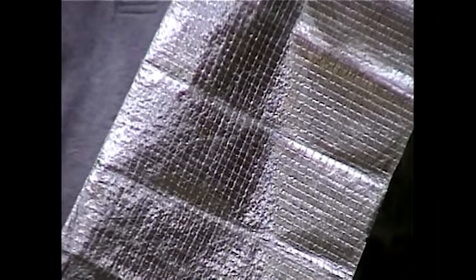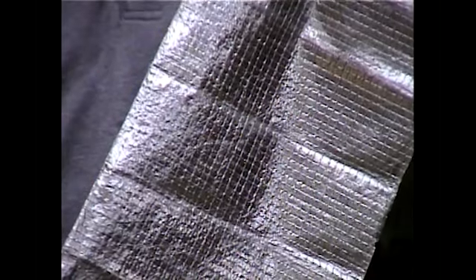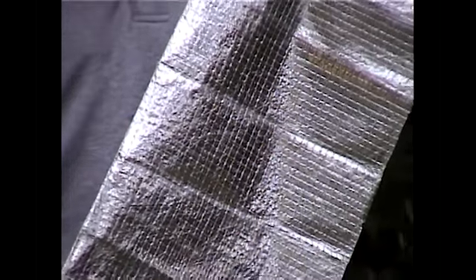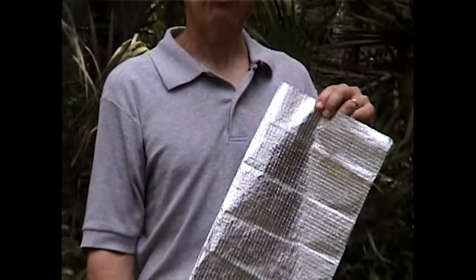In existing homes, you can add radiant barriers under the rafters to reduce heat gain. It works by reflecting heat back towards the roof. The heat can then exit the ridge vent. In the process, this creates a natural flow of bringing in cooler air from the soffits, helping to keep the attic much cooler.